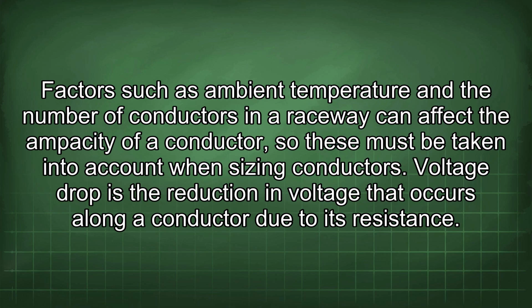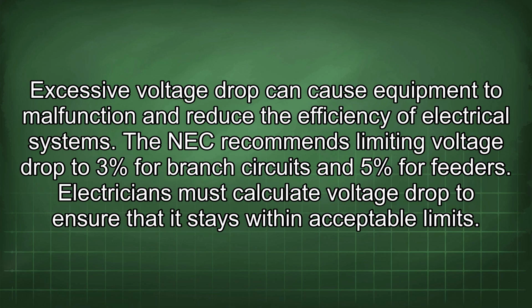Voltage drop is the reduction in voltage that occurs along a conductor due to its resistance. Excessive voltage drop can cause equipment to malfunction and reduce the efficiency of electrical systems. The NEC recommends limiting voltage drop to 3% for branch circuits and 5% for feeders. Electricians must calculate voltage drop to ensure that it stays within acceptable limits.